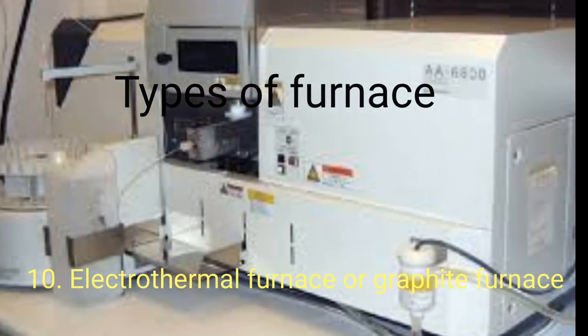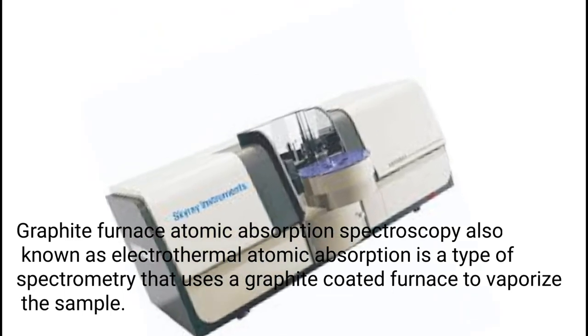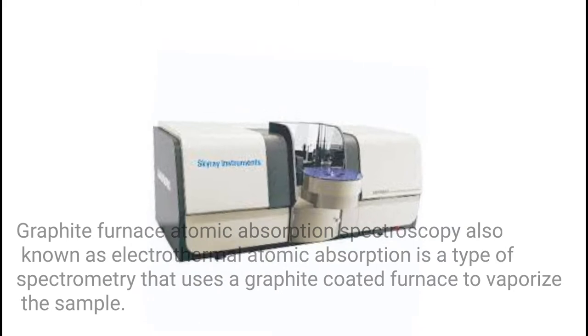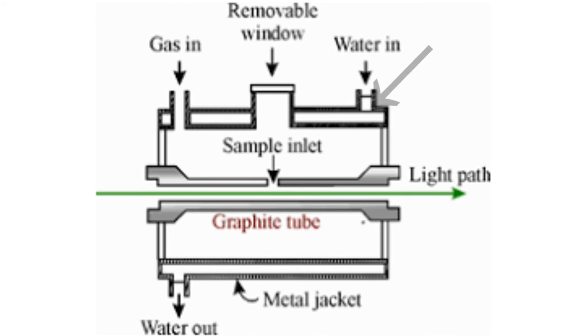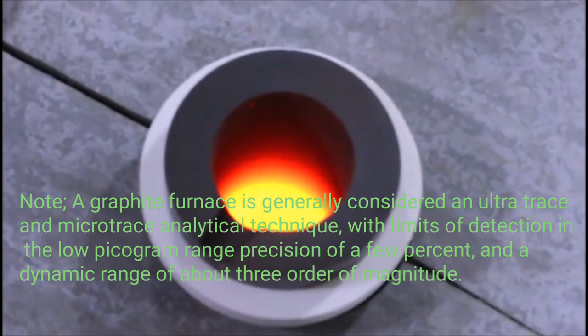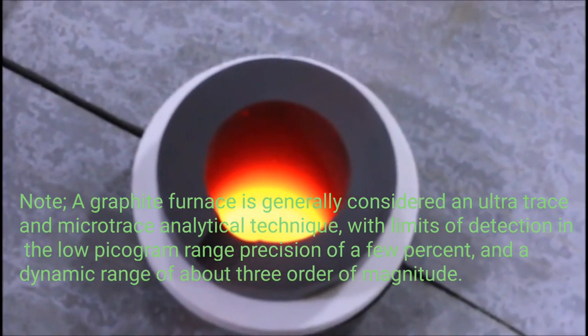Type 10: Electrothermal Furnace or Graphite Furnace. Graphite furnace atomic absorption spectroscopy, also known as electrothermal atomic absorption, is a type of spectrometry that uses a graphite-coated furnace to vaporize the sample. A graphite furnace is made up of a graphite tube at both ends with a hole in the center for sample introduction. The tube is encased with graphite electrical contacts at both ends that serve to heat the sample. A supply of water is used to keep the graphite furnace cool, and an external stream of inert gas flows through the tube carrying away vapors from the sample matrix.